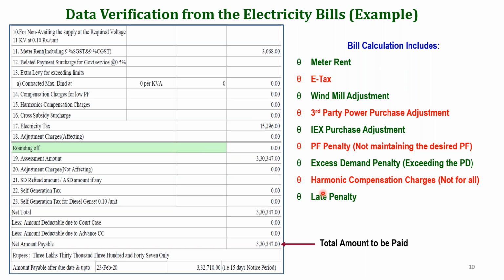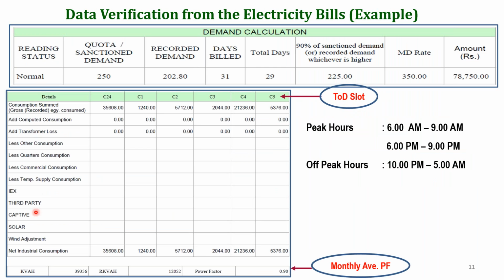Recently, we conducted an audit in Chennai for a facility with a maximum demand of 5 MVA, where 60% of the electrical power is purchased from IEX and 20% is adjusted from windmill. So this information will also be available in the page allotted for the HT. Now, in the same HT bill, you can see for the particular month, this is the sanctioned demand, and this is the recorded demand.